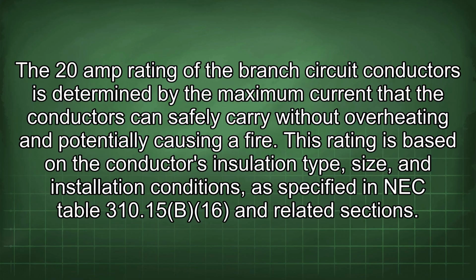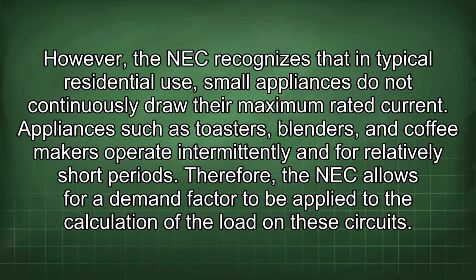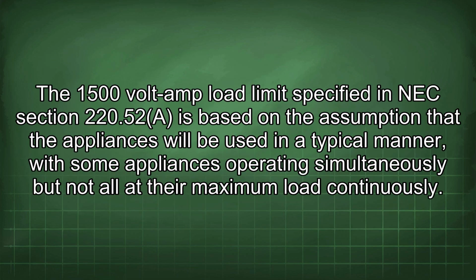310.15(B)(16) and related sections. However, the NEC recognizes that in typical residential use, small appliances do not continuously draw their maximum rated current. Appliances such as toasters, blenders, and coffee makers operate intermittently and for relatively short periods. Therefore, the NEC allows for a demand factor to be applied to the calculation of the load on these circuits. The 1500 volt amp load limit specified in NEC section 220.52 is based on the assumption that the appliances will be used in a typical manner, with some appliances operating simultaneously but not all at their maximum load continuously.